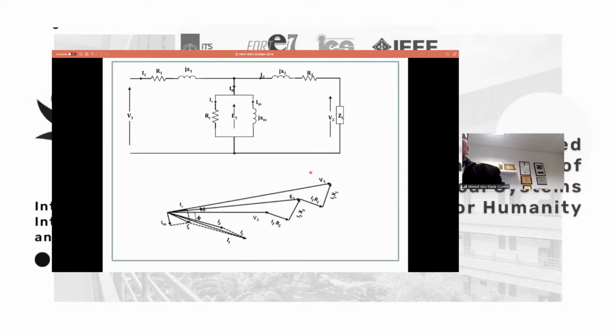The idea came to me from this simple equivalent circuit of the transformer. You may notice that there's no capacitor here because I don't have high frequency. I will perform the test at 50 hertz. At 50 hertz, the capacitor is almost an open circuit, right? 1/(2πfC). So that's the phasor diagram we all know. And what I thought about is to plot V1 minus V2, the voltage difference between the input and the output of each phase, against the input current.